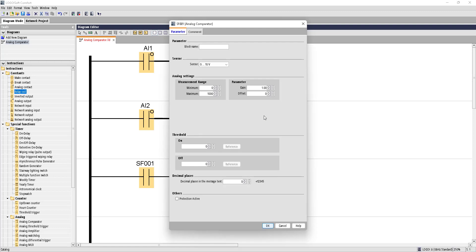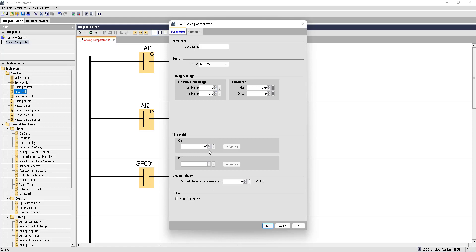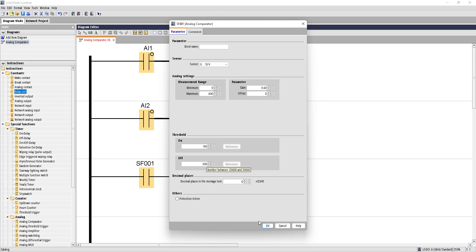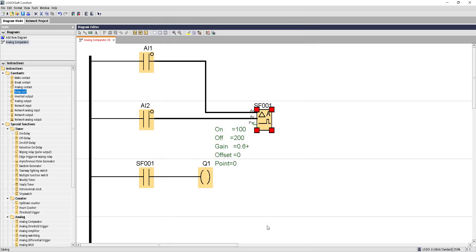For example, suppose we have 0 to 600 value, and our analog comparison will be based on this value. Now let's say you want to turn on your load when the analog sensor reaches 100 of value, and you want to turn off when it exceeds 200. So basically it's the limit you are setting here, that is 100 to 200. Between this range, our output will turn on, and outside this limit our output load will be turned off.